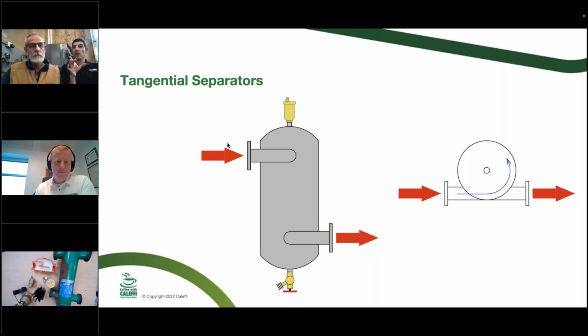The big vessel itself will help separate air because it's going to slow down, but to get that full vortex effect, it has to be at a target GPM, which it won't always be if you had a variable speed pump.